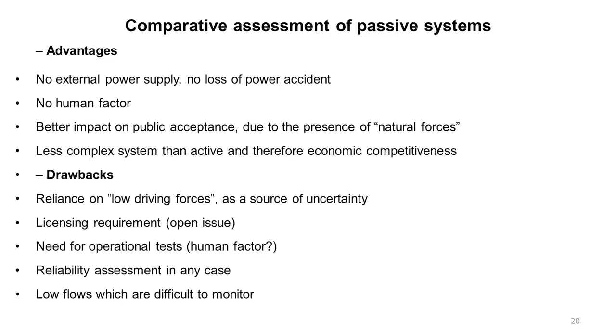In a comparative sense, the advantages of passive systems are: no external power supply required, so no loss-of-power incident can be conceived; no human factor since it is based on natural forces (though some human factor may be involved if a button must be actuated); and better impact on public acceptance because the public can accept reactors dependent on natural forces like gravity and buoyancy — gravity is not going to fail you.